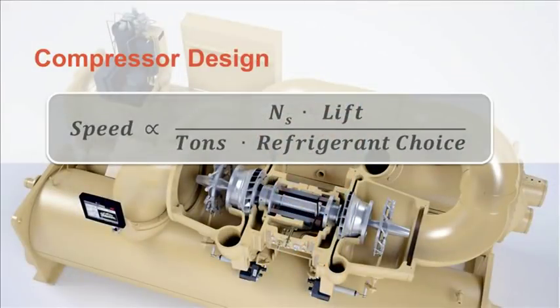To begin to understand how compressor design and speed impact overall design, let's take a look at the specific speed formula, or what is the most efficient speed to spin at? To answer this question, we need to look at three significant components. Lift, which speaks to the size of the impellers. Tons, which speaks to the volumetric flow through the compressor. And refrigerant choice, which determines volumetric flow and is a significant determiner of efficiency.